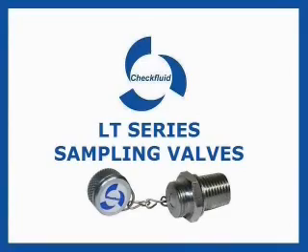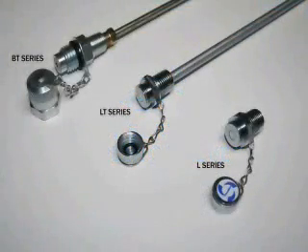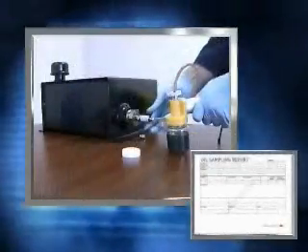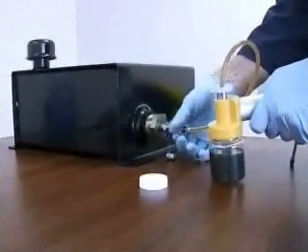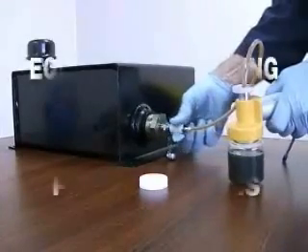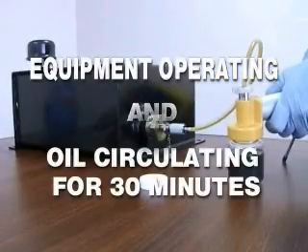In this 3-minute video, we will show how to use the Checkfluid LT Series High Flow Sampling Valve to draw a representative oil sample that can be accurately analyzed time over time. The LT is permanently mounted to draw the most active oil while the equipment is running. It is important that the equipment has been operating and the oil circulating for at least 30 minutes prior to sampling.